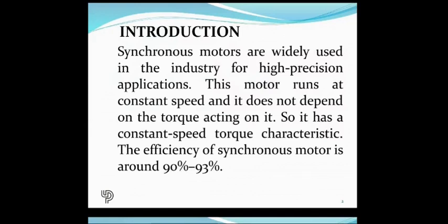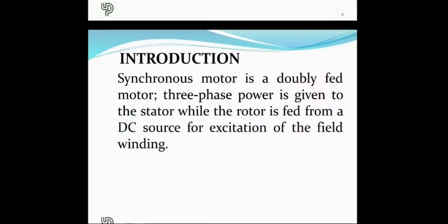The downside is that it needs two inputs. One is the three-phase AC input to the stator, and the other one is the DC input to the rotor. It's a doubly fed motor, as I already said. And another disadvantage is that the motor is not able to start by itself. You have to do something.